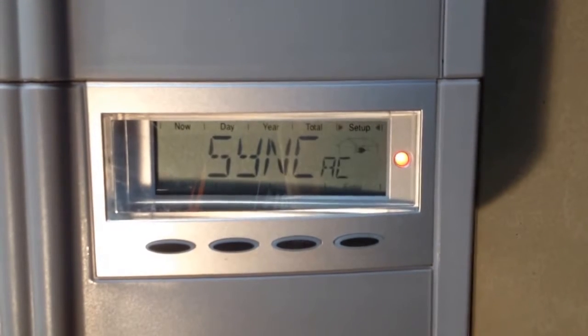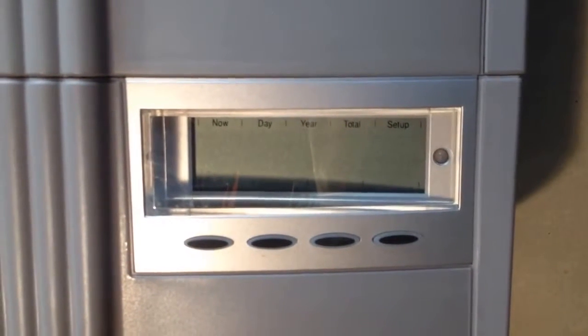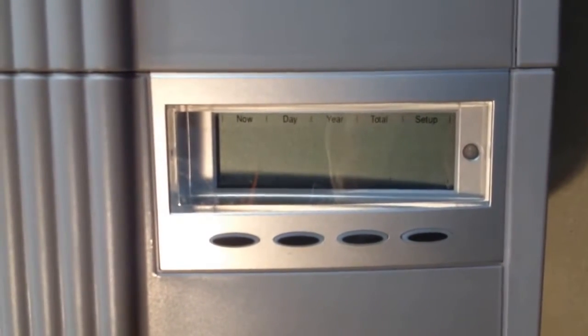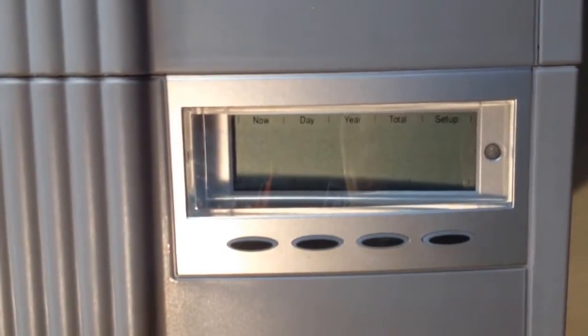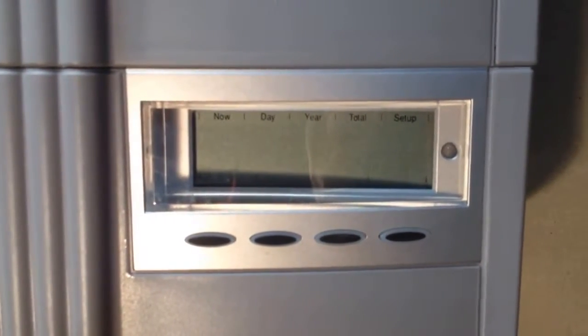State 104, which means it detects that the grid frequency is out of range on the inverter. And there we go, it's gone totally blank. Now, if you wait a few seconds — usually about 30 seconds or so is a good time — and then try and reboot the inverter.